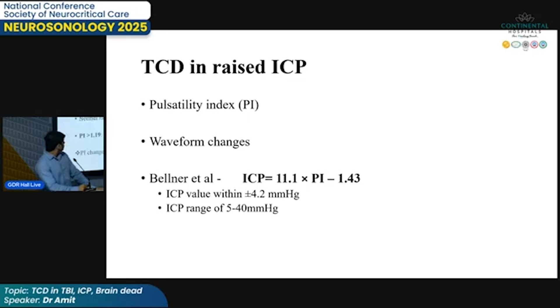Since the basal cerebral arteries have compliant walls, they are more vulnerable to external pressures with raised ICP. And this ICP causes changes to the flow velocities and the spectral waveform, which can be non-invasively observed with transcranial Doppler. So the TCD-based non-invasive ICP estimation is based on 3 things. First is the pulsatility index. Second is the waveform changes. And the third is a mathematical model, such as the one provided by Bellner et al., which gives an ICP value within a range of 5 to 40 millimeters of mercury with a sensitivity and specificity of almost 90%.